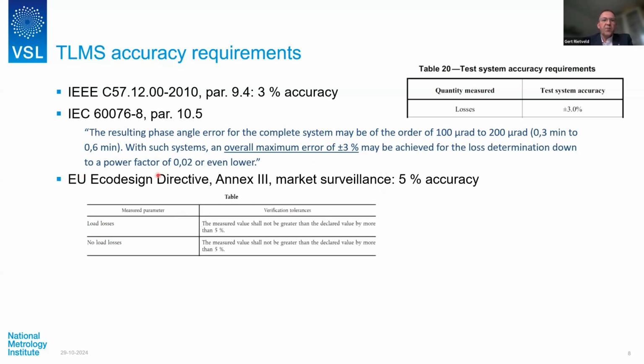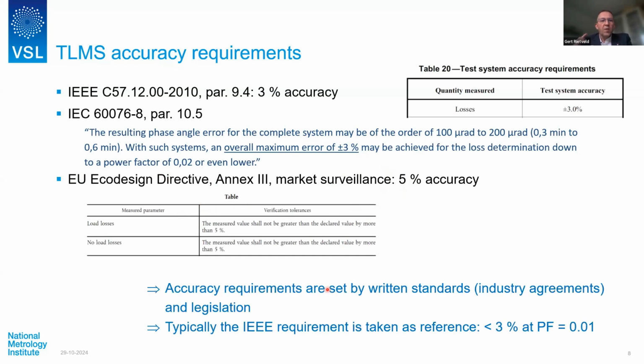The Eco-design directive relevant for Europe states something about 5% accuracy. So in summary, there are accuracy requirements on this loss measurement set by written standards, which are industry agreements, and legislation, the EU requirements, that is part of legislation. But typically, to give a ballpark number, this IEEE number of 3% at a power factor of 0.01 is taken as the reference, as the minimum required accuracy.